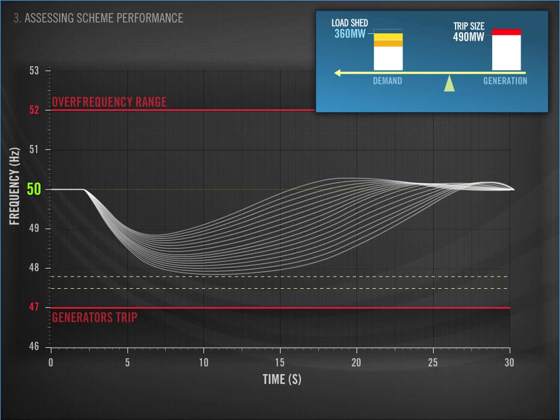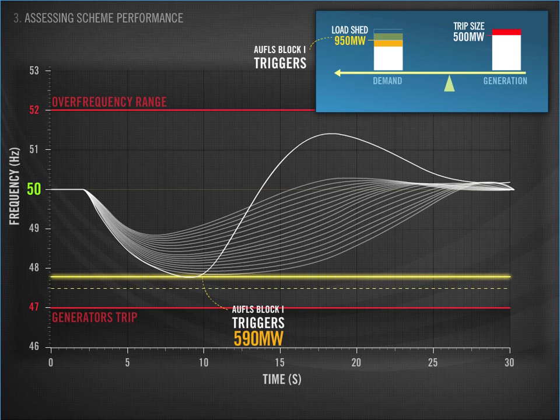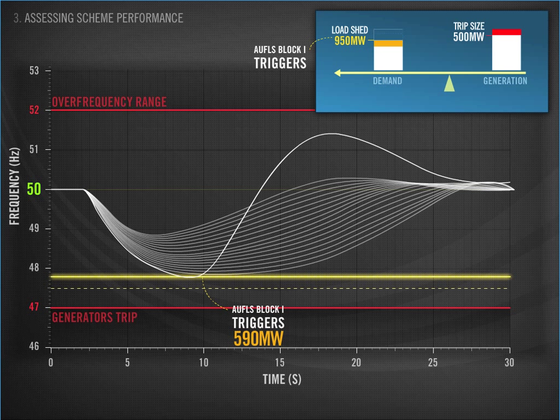As soon as the frequency goes below 48 Hz, we are in UFLS territory. Here is the first event that triggers UFLS Block 1. We have a 500 MW loss of generation, which results in a total of 950 MW of load being shed. This includes both interruptible load and UFLS. It is worth noting that during an event, the system is not static, and most generators are increasing their output in response to the frequency falling. The amount of load shed needed is unlikely to equal the size of the event exactly.